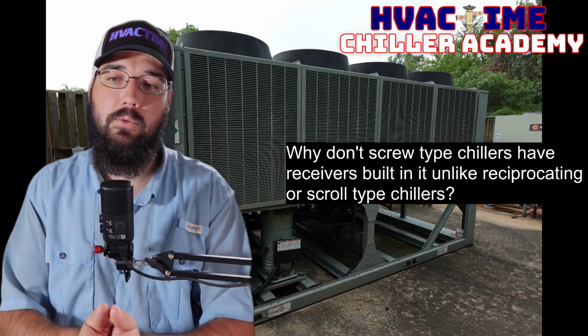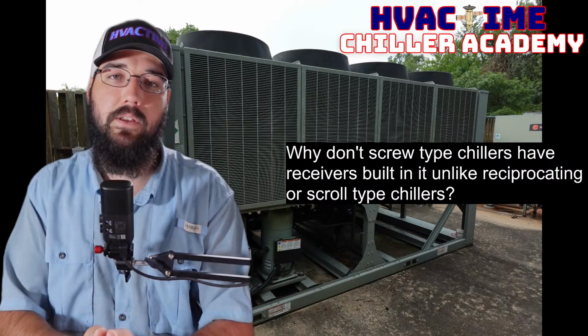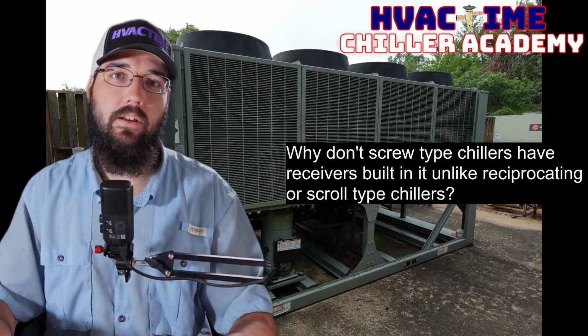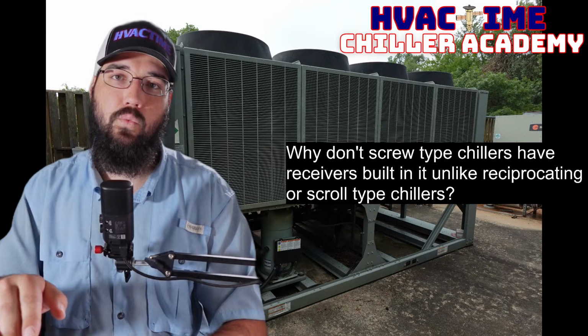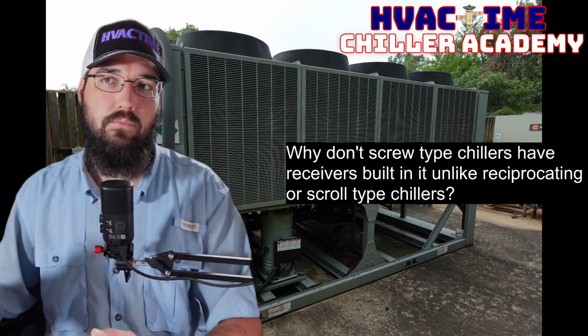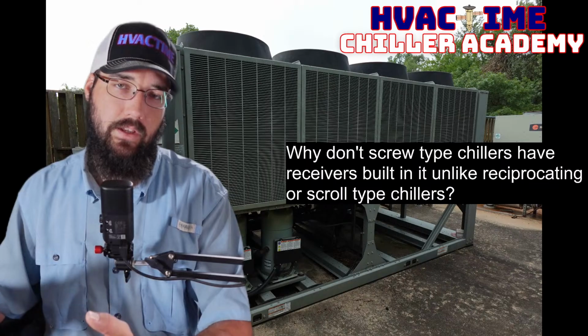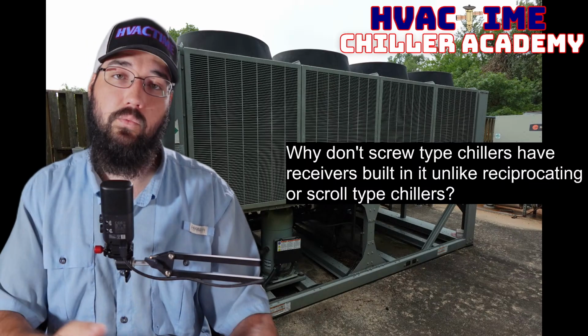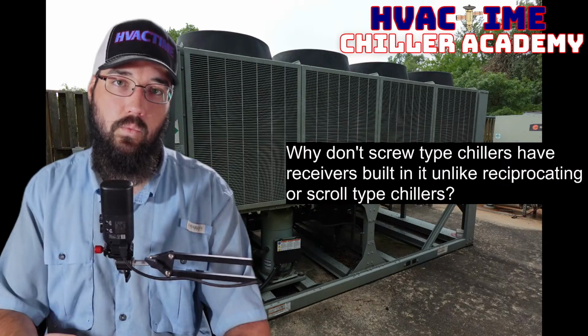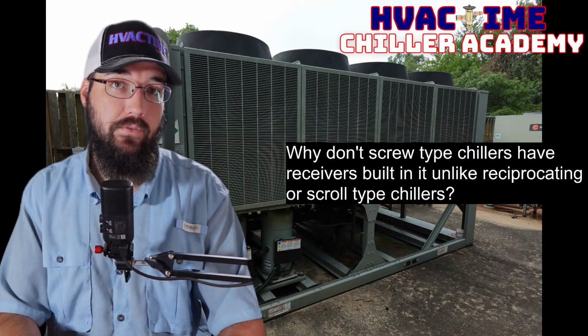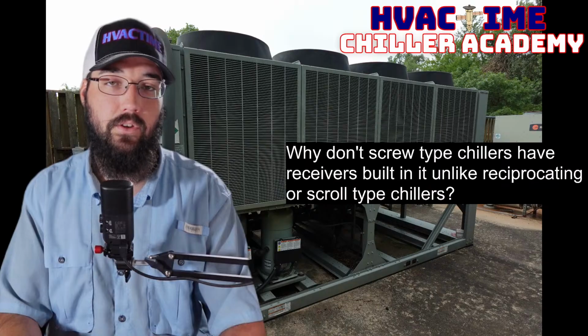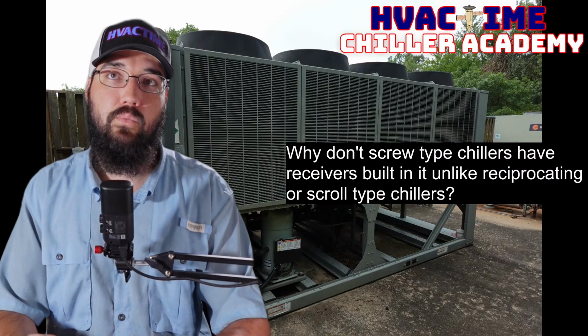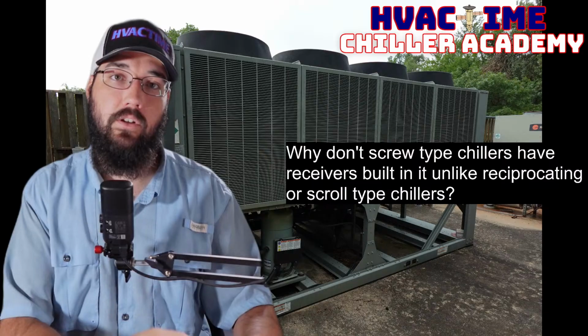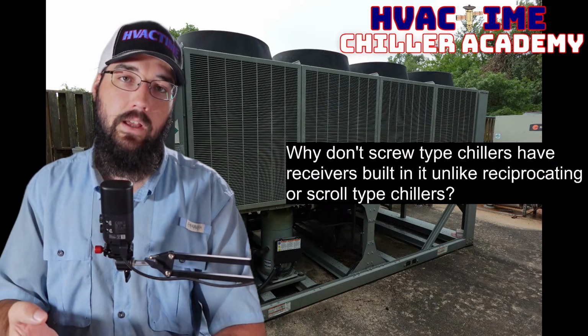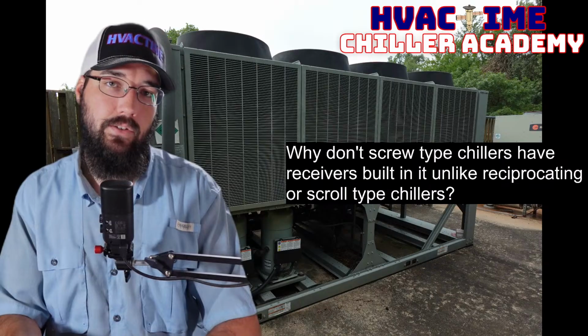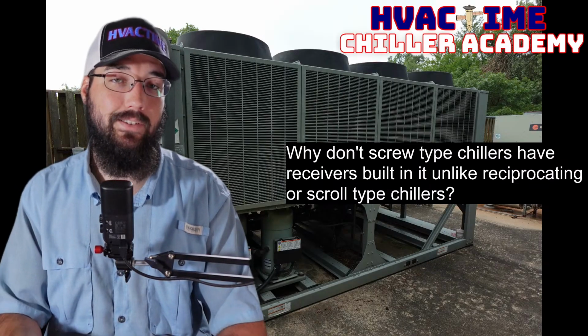So I think that would be the most basic breakdown I would want to give on that, as to why some chillers may use a liquid line receiver versus others don't. It's going to come back to, one, how much can the compressor unload itself to regulate that refrigerant flow so that we can tune the flow to the load. And then two, what kind of swings does that chiller expect to see?